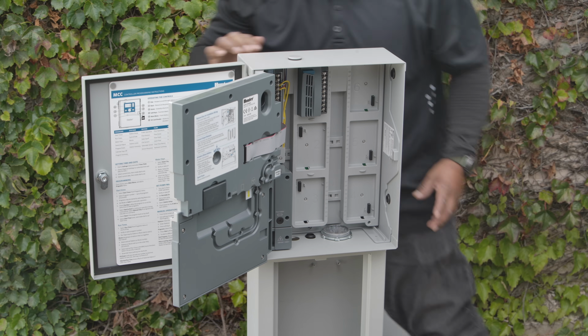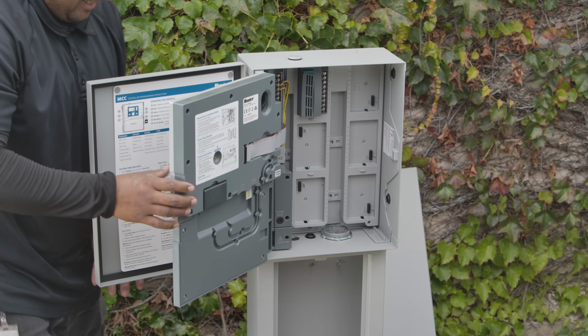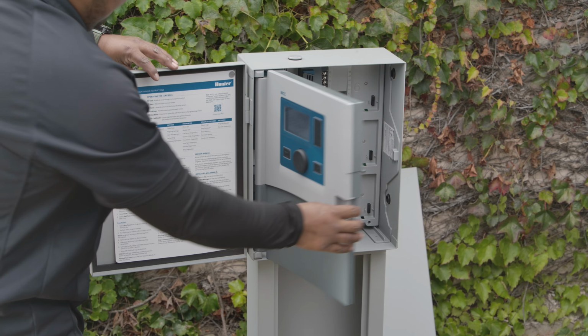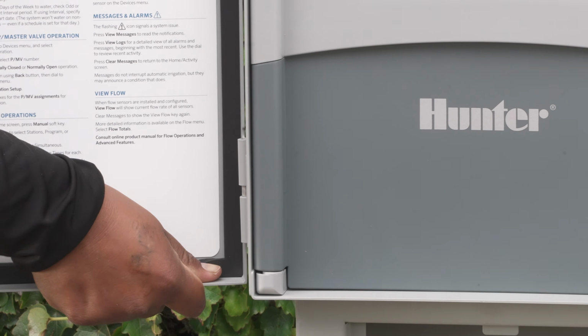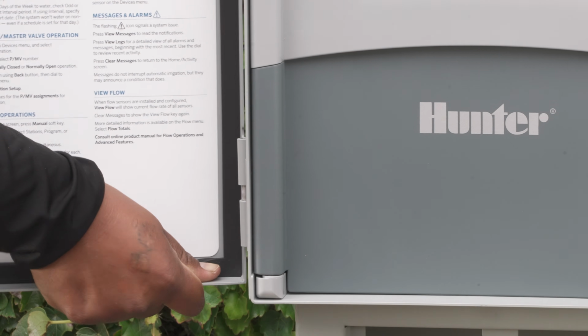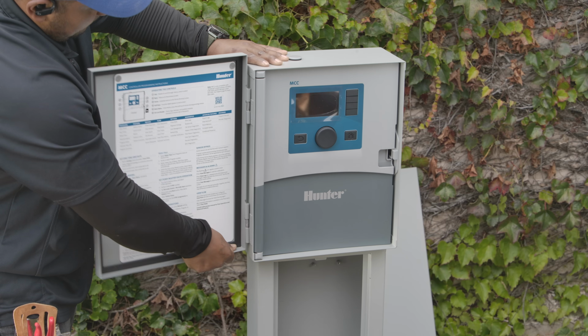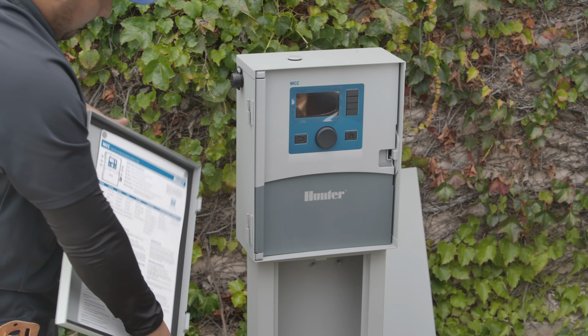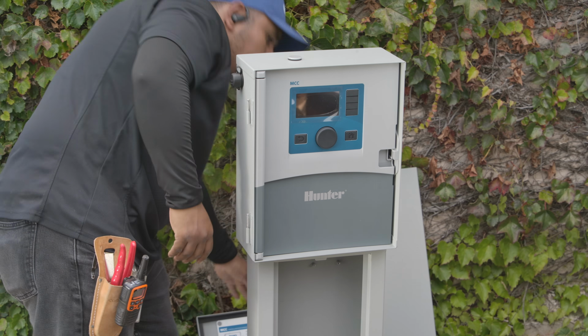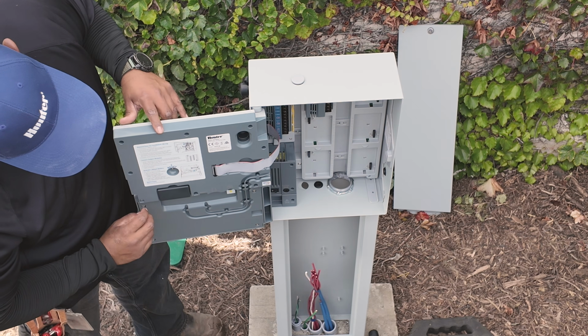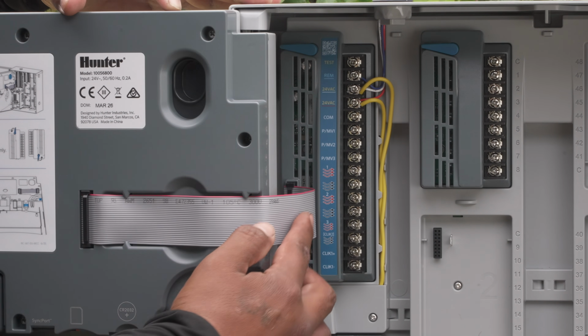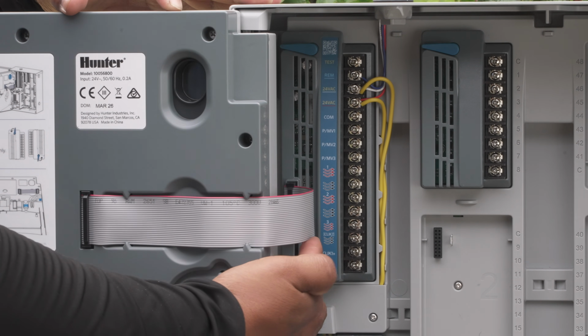With the controller mounted, it's time to connect the primary AC power wiring to the transformer. It's easiest to remove the external and interior doors during the installation process. With the outer door open, lift it straight up to remove it from the hinges. Next, open the inner door and locate the gray ribbon cable connecting the face pack to the controller housing.